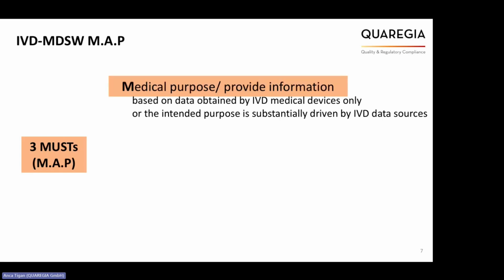So the M stands for medical purpose or provide information, as we saw in the definition. And in the case of IVDs, this medical purpose or information provided has to be based on data obtained by IVD medical devices only, or the intended purpose must be substantially driven by IVD data sources. So the software can analyze data that comes from IVD devices, but its medical purpose has to be within the scope of the in vitro diagnostic regulation.